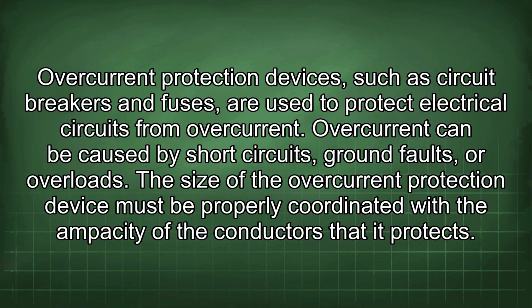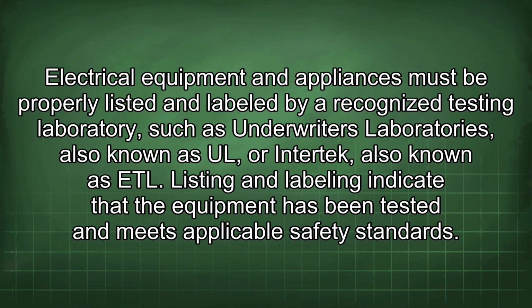Overcurrent protection devices, such as circuit breakers and fuses, are used to protect electrical circuits from overcurrent. Overcurrent can be caused by short circuits, ground faults, or overloads. The size of the overcurrent protection device must be properly coordinated with the ampacity of the conductors that it protects. Electrical equipment and appliances must be properly listed and labeled by a recognized testing laboratory, such as Underwriters Laboratories, also known as UL, or Intertek, also known as ETL. Listing and labeling indicate that the equipment has been tested and meets applicable safety standards.